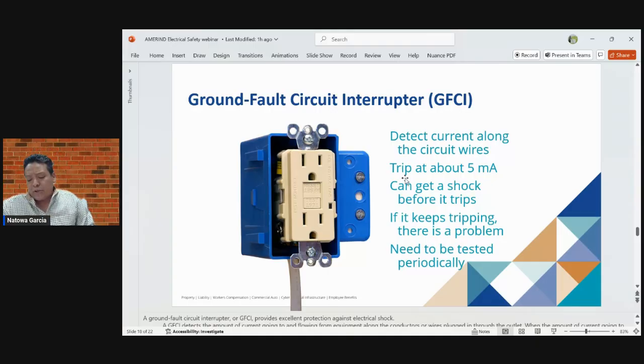The ground fault circuit interrupter trips at about 5 milliamps in a fraction of a second. It's still possible to receive a brief shock, but it trips so quickly that the shock won't be harmful. If a ground fault circuit interrupter keeps tripping, a serious problem may exist. Don't assume the circuit interrupter is defective and substitute a non-circuit interrupter outlet.